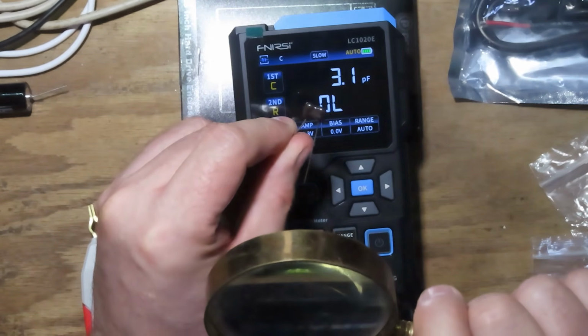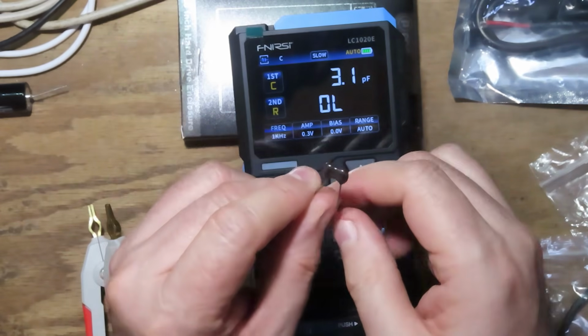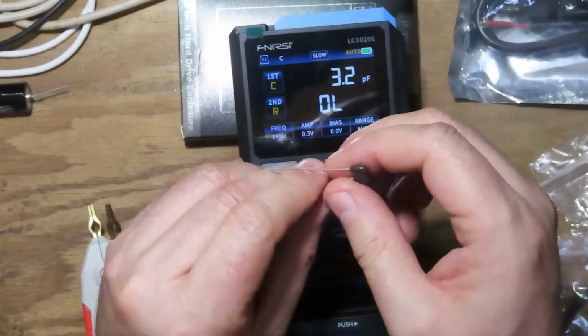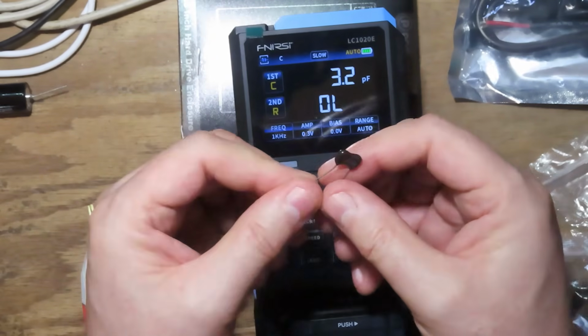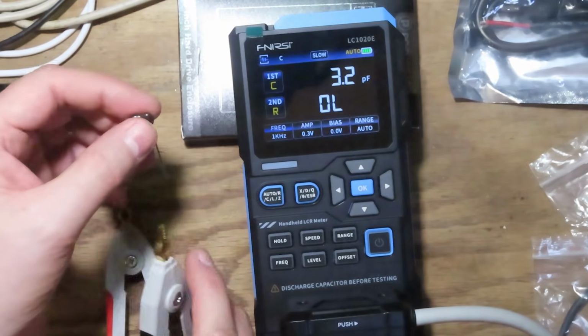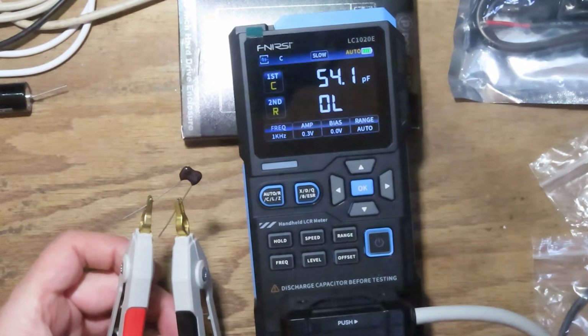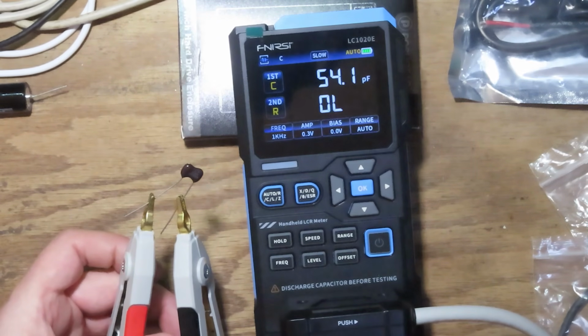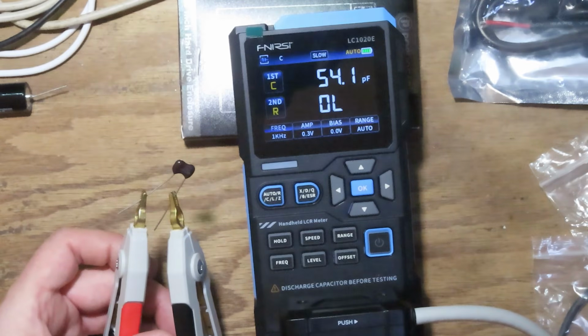What do we have here? 51 plus or minus 3%, 500 volts. So this is a low value — we probably want to go higher in frequency. Let's measure it at 1 kilohertz and see what we see. Okay, 54 picofarad — we're actually reading it okay at 1 kilohertz. What was that suggested frequency range?